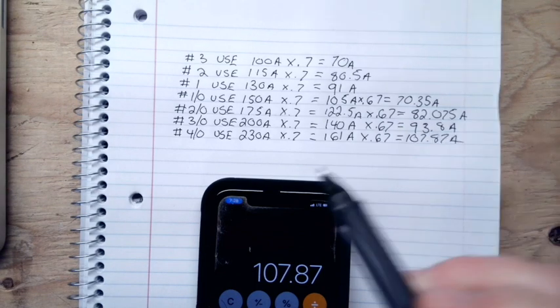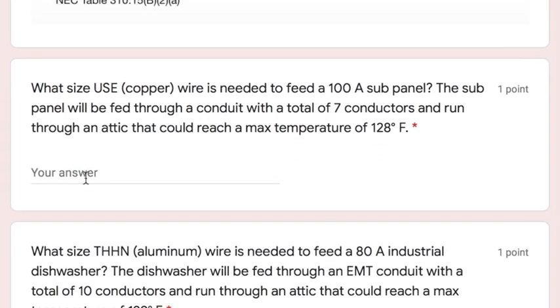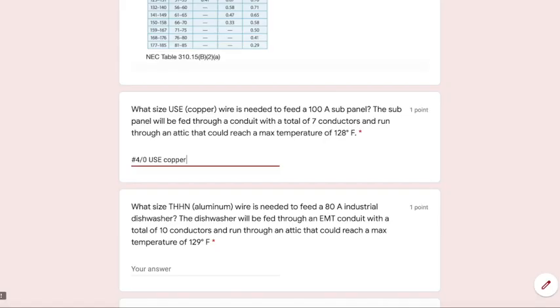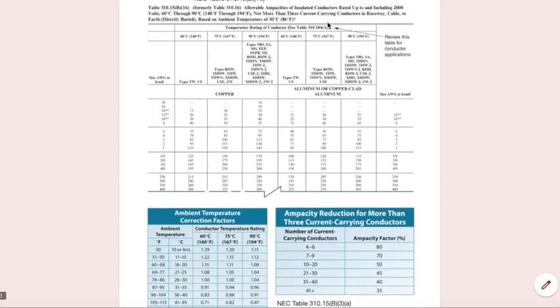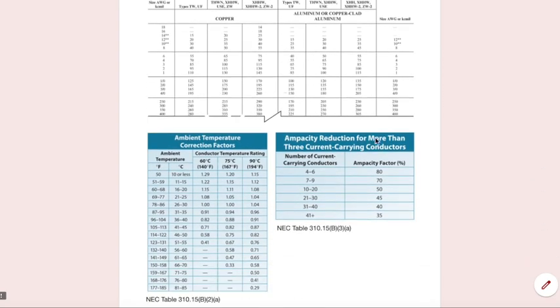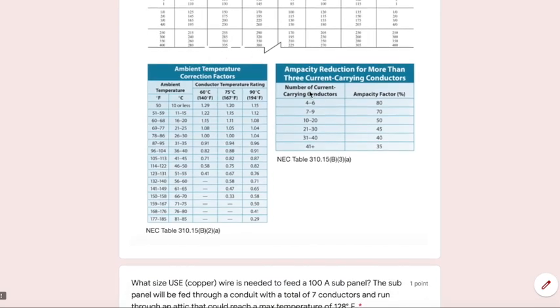So for this question, to answer it, we need a number four-ought, 4-0, U.S.E. copper. This really isn't very hard, right? It's about knowing where to find the information on these tables. We start off with the 310-15B-16, then we apply adjustment factor if we need to, and we apply correction factor if we need to. It's important that you just see how this stuff links up. Once you figure that stuff out, it's just a procedural process of starting with what works all the way down, or what you think will work all the way until you find what actually works.